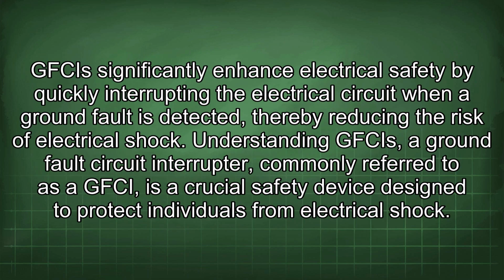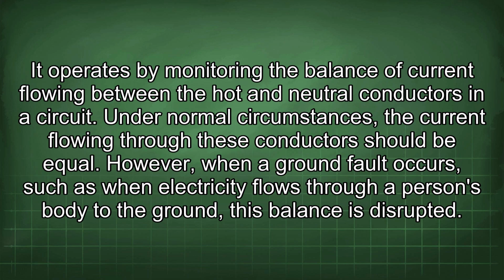GFCIs significantly enhance electrical safety by quickly interrupting the electrical circuit when a ground fault is detected, thereby reducing the risk of electrical shock. A GFCI, or ground fault circuit interrupter, is a crucial safety device designed to protect individuals from electrical shock. It operates by monitoring the balance of current flowing between the hot and neutral conductors in a circuit. Under normal circumstances, the current flowing through these conductors should be equal.